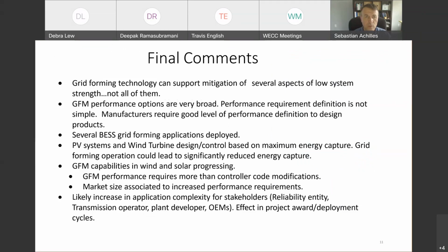First bullet: grid forming technology can support mitigation of several aspects of low system strength, but not all of them better than other approaches. Not in everything will grid forming be better than grid following, or at least not initially. The key differentiation for grid forming is in really low system strength with local loads, that high IBR penetration scenario I described earlier in the slides. That's where grid forming is expected to do better in terms of steady state stability, control instabilities, and surviving faults. So that's the strength of grid forming.